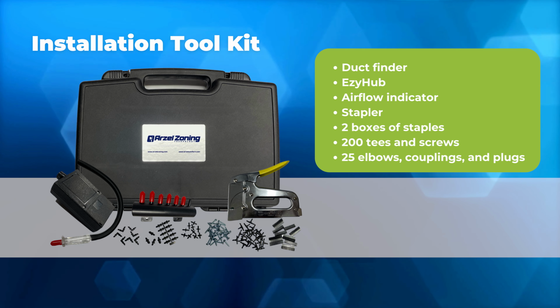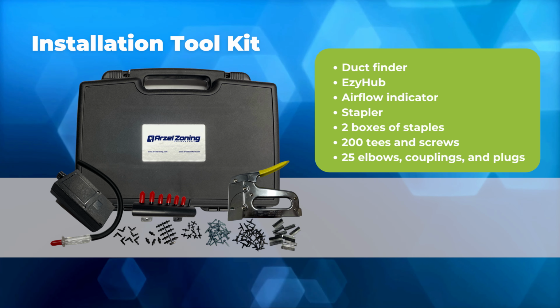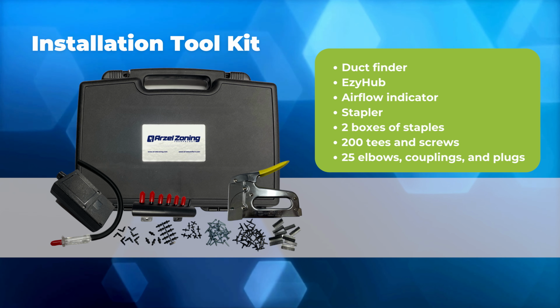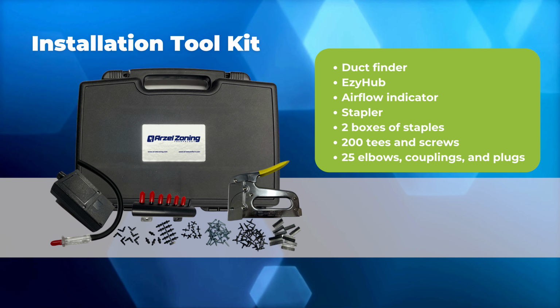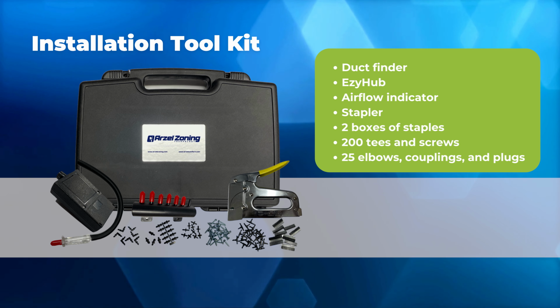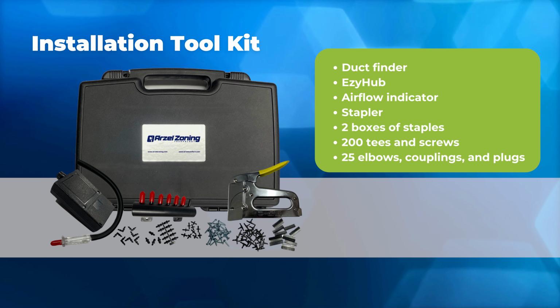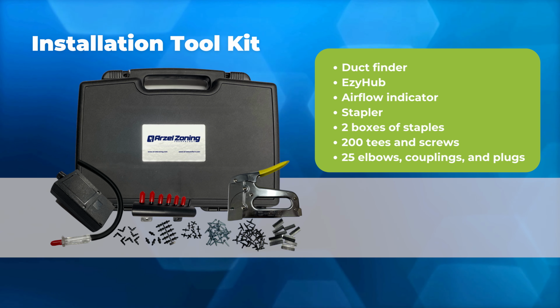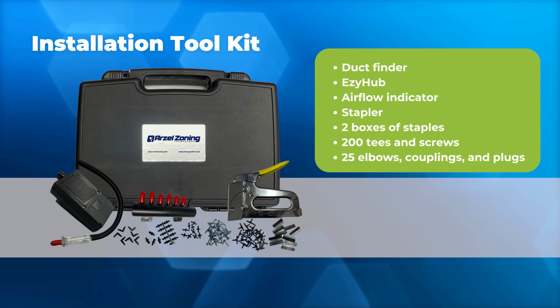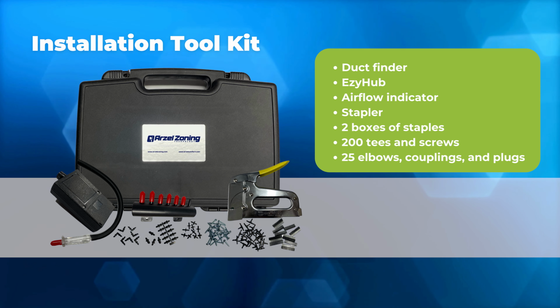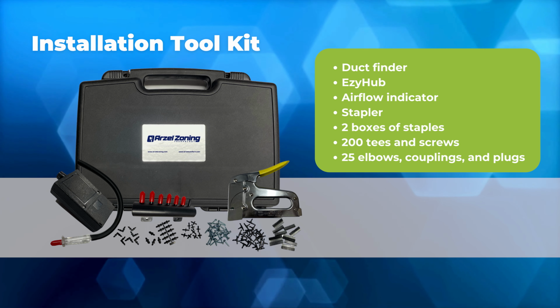It also comes with our Easy Hub, which is that yellow piece there in the front. This is going to be used for the Insertas, Regi dampers, and the EzyFit dampers. Because you're running that tubing all through the ductwork and you're coming out in a centralized location, usually in the mechanical room, when you come out of the ductwork with all that tubing, this allows you a home run to put all your tubing onto. And then you can just run one tubing back to the panel from there. So essentially it acts like a manifold on a boiler. It just makes it a cleaner look.